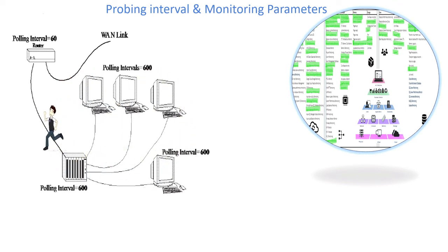Best practices says probing interval should be 60 seconds multiplied by 3 times. This means here this little guy will run and pick up the probe from the machine every minute for 3 times. Based on the information, the monitoring hub will decide if the breach of threshold is consistent for all the 3 times. If yes, it qualifies for alert.